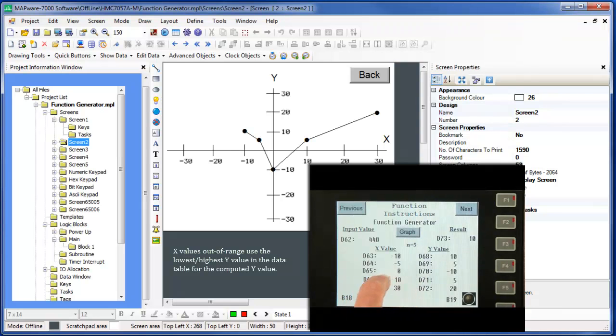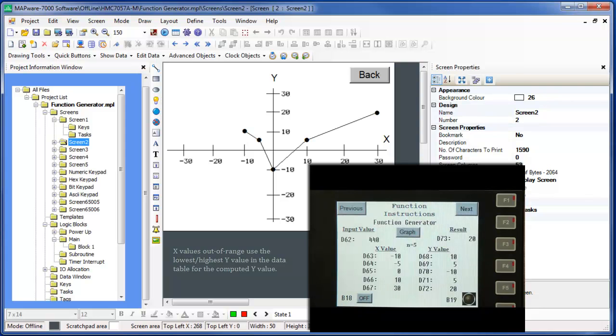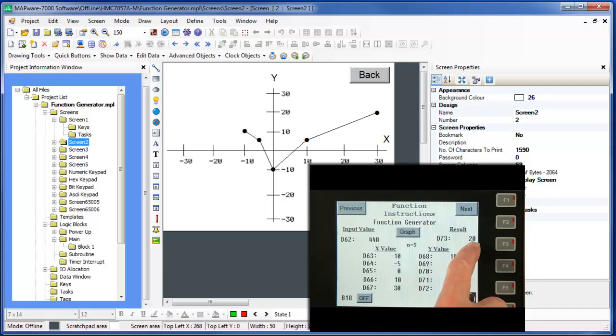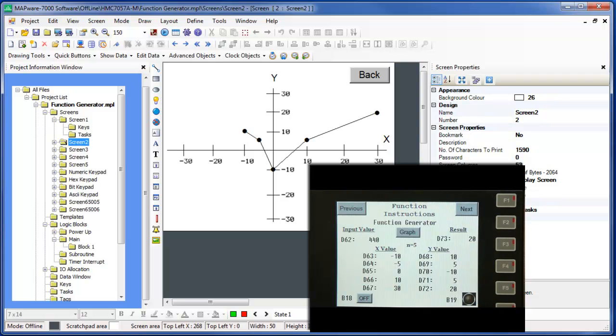What if the X value is more than the largest X value in the table? As we expected, if an X value is entered that is higher than the highest X value of the data table, the function generator uses the Y value associated with that high X value as the computed Y value.